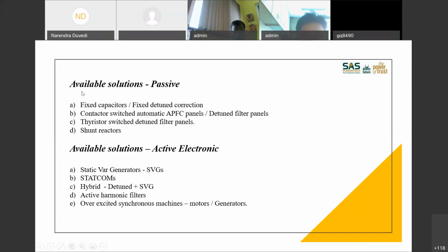Which are the available solutions for the problems we discussed so far? There are basically 2 types of solutions, passive and active, or their combination. Passive: fixed capacitors, fixed detuned corrections, contactor switched automatic APFC panels, detuned filter panels, thyristor switched detuned filter panels, shunt reactors. These are all passive corrections. Passive corrections typically will have more life if installed with proper calculations and proper prior study, and maintenance cost is comparatively very less. Capacitor replacement is needed after every 5-6 years, and for reactors probably no replacement for the initial 10 years. So these are passive solutions.